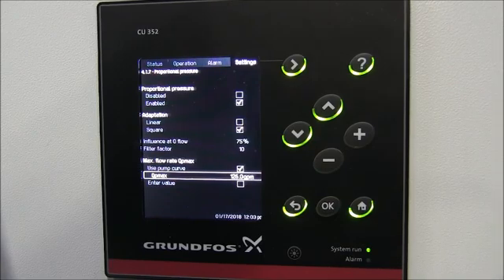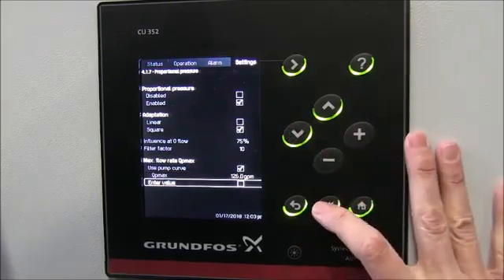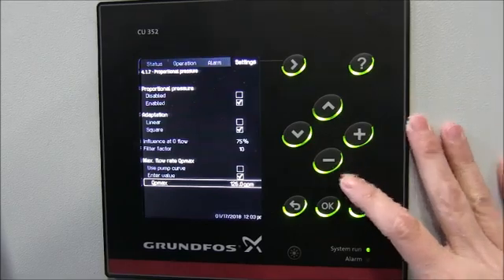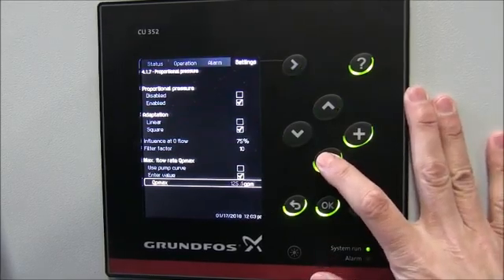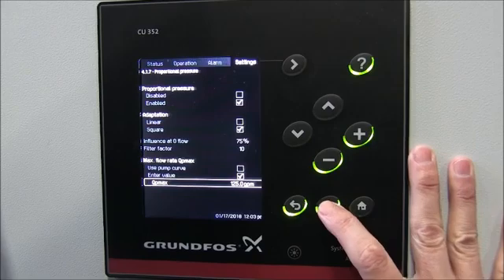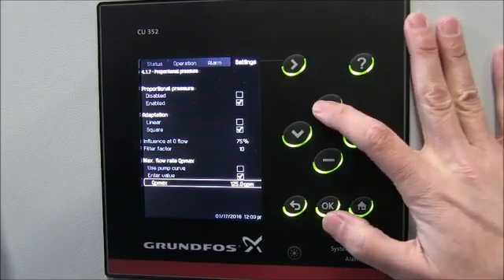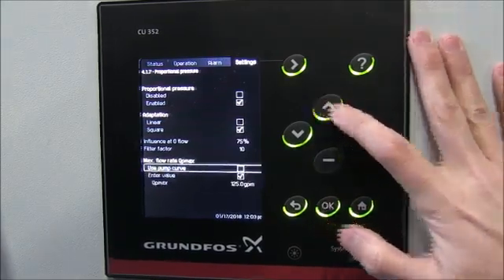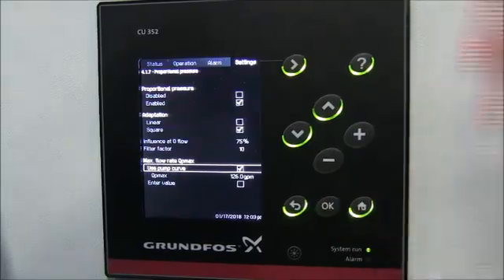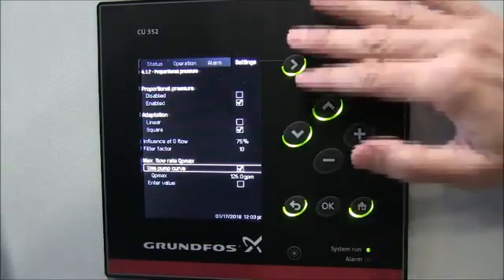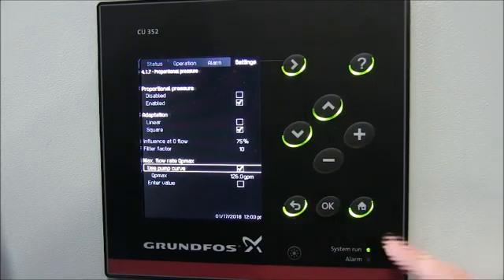If you wanted to customize your proportional pressure — in other words start the control curve at a lower flow rate — you could hit Enter Value and adjust it down. For example, setting it to 125 GPM would start the curve there. We're going to go ahead and use the pump curve, which is the most common approach. That's everything we need to do to set up proportional pressure control.